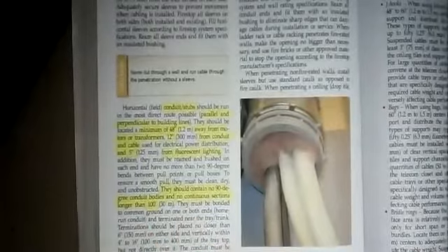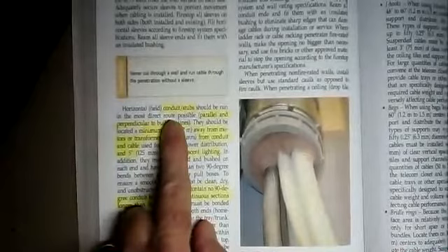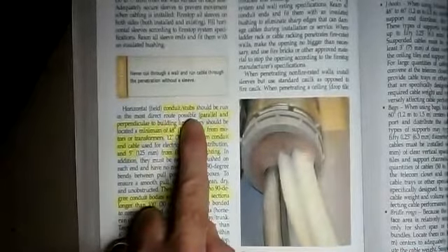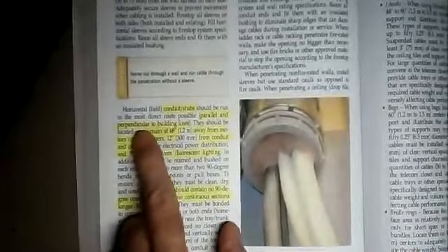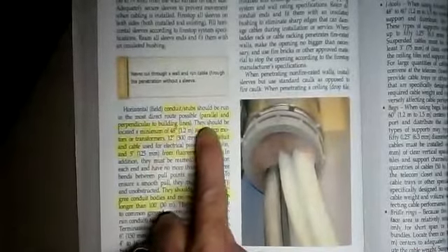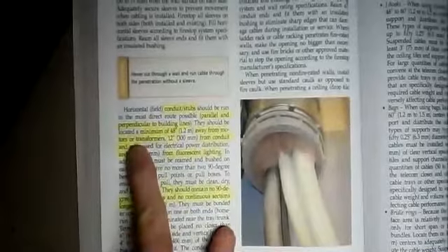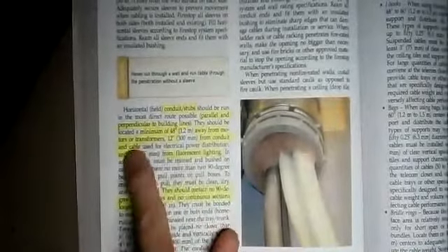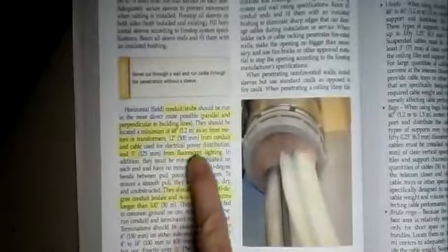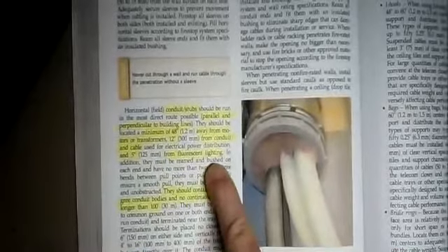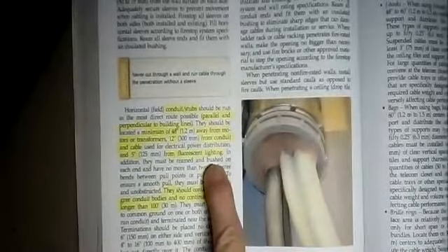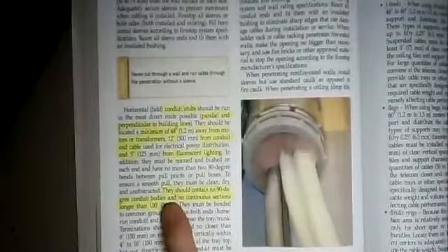So here on the bottom of page 10, left-hand side, it says horizontal conduit or stubs, that's a sleeve through a wall, should be run in the most direct route possible, parallel and perpendicular to the building lines. They should be located a minimum of 48 inches away from motors and transformers, 12 inches from conduit and cable used for electrical power distribution, and 5 inches away from fluorescent lighting. So deja vu all over again. That's the requirement for all of these different types of runs.